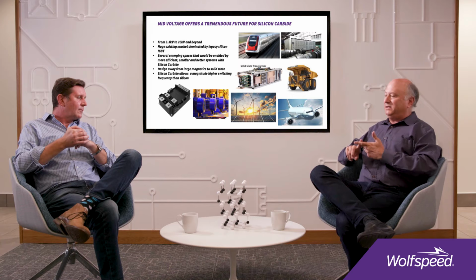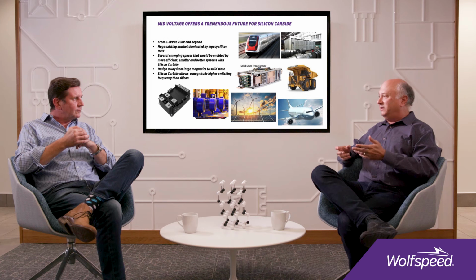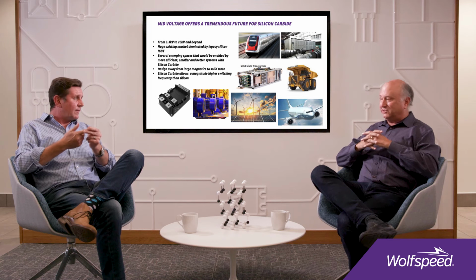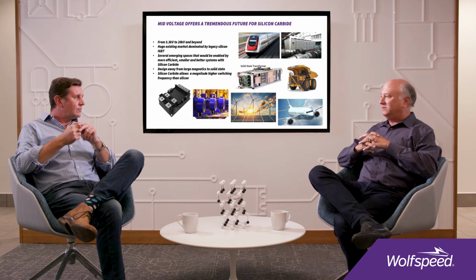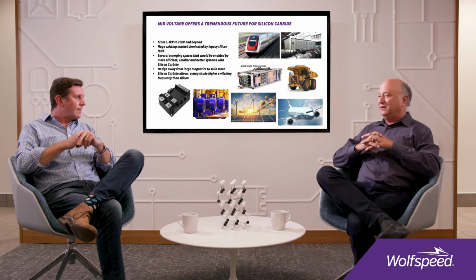So let's imagine instead that you have silicon carbide, 3.3 kV modules or 6.5 kV modules. You could pull that down with a solid state transformer, push that big heavy transformer off the train. Saves a lot of space, a lot of weight, and then you can do the motor drive much more efficiently. Now instead of a 4-level design, maybe you do a 2-level. Simplicity, more efficient, simpler design, fewer parts, etc., and far more efficient. So even at 3.3, it's an order of magnitude improvement in switching losses, and there's no comparison to what silicon carbide can do at those frequencies.